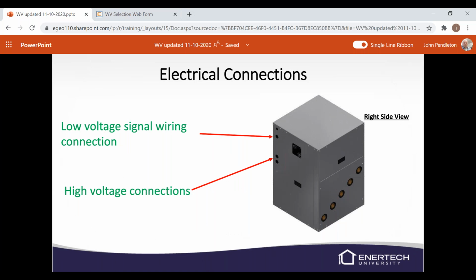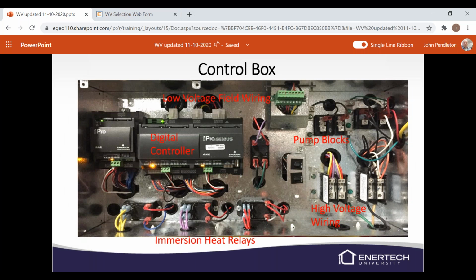Electrical connections. We got low voltage wiring in the upper portion. The high voltage is in about midway, and that's looking at kind of the right side of the unit there. This is the control box. We've got the digital controllers, the iPro. We've got some heater relays. That green little box in the upper middle portion is your removable terminal strip for your low voltage. And then you have your high voltage coming in.